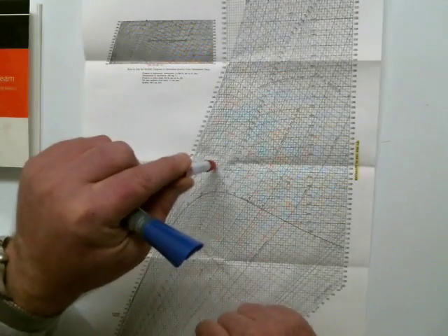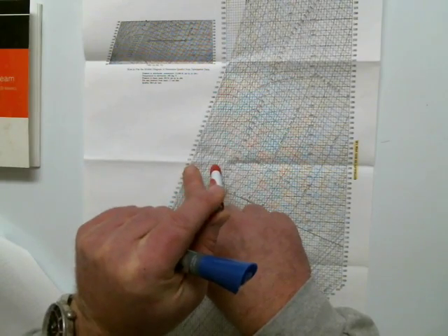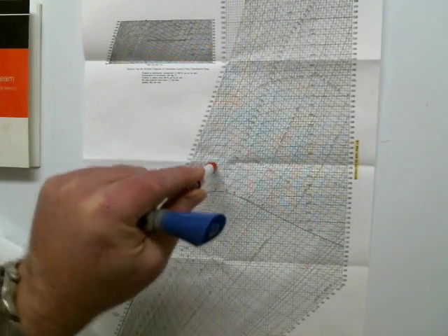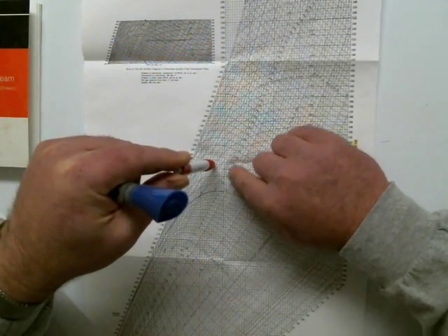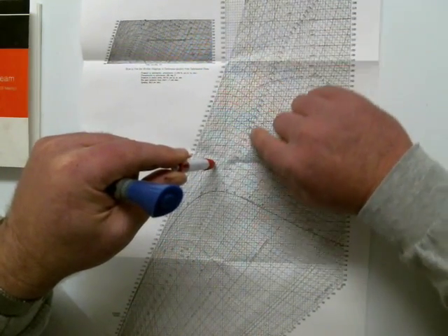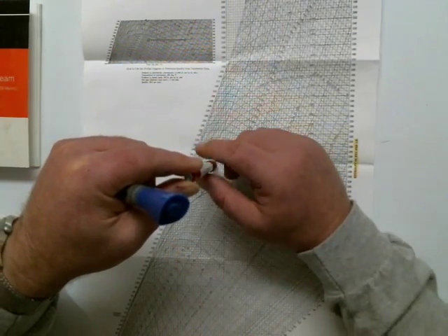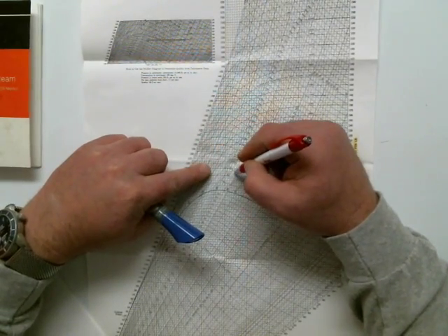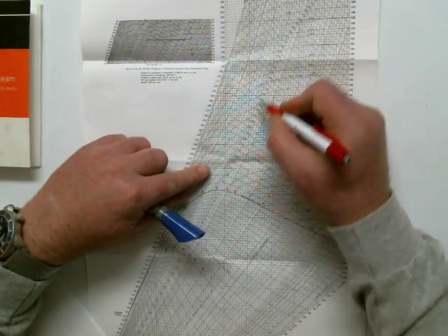Now I can see the enthalpy right there. I can go over here and see that it's about 1,260 BTUs per pound mass if I existed up there with superheat. Then these other lines exist. These lines, right, as numbers, these are the degrees of superheat. And we know that I had about 56 or so degrees of superheat, and that's what these numbers right here are, degrees of superheat.